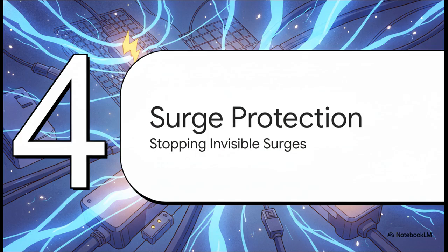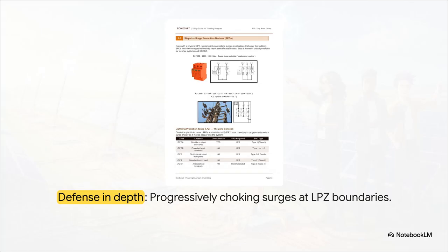Which brings us to Section 4, Surge Protection Devices, because just stopping the physical strike is only half the battle. See, intercepting the direct physical strike is incredible. But even with those beautiful air terminals doing their job, lightning still induces massive voltage surges in all the cables entering your buildings. So, the solution? Dividing the plant into lightning protection zones, or LPZs. I love this concept. The philosophy here is defense in depth. You essentially divide the plant up and install surge protection devices at literally every single boundary. You are progressively choking out the surge energy, step by step, as it desperately tries to move deeper into the sensitive heart of your system, like your inverters and SCADA panels.